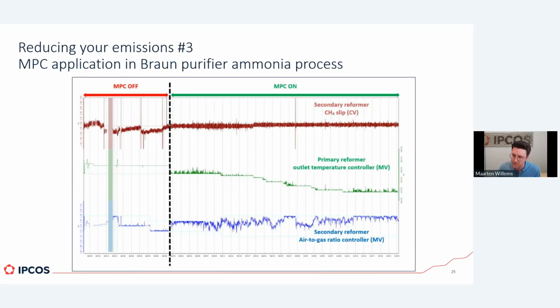Whereas on the right, with an APC project or with model predictive control, you can much more finely regulate that. Now, on top, you see that methane slip. As I told you, there are constraints and there are handles, and this methane slip was actually the constraint in this process. The methane slip is the amount of methane that goes to the secondary reformer without being changed into hydrogen. What you can even see is that after a few weeks of using the APC, they started to trust the system and increased their constraint even a bit. Whereas before, without the APC, it's a bit all over the place. It's much more difficult to maintain that constraint.